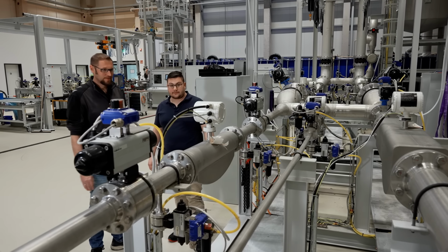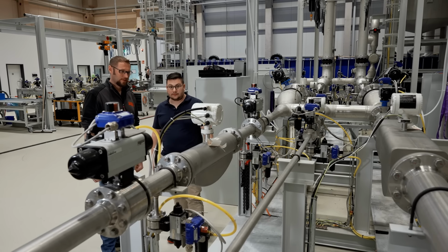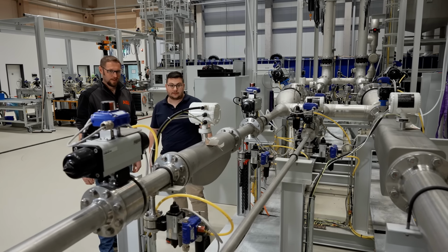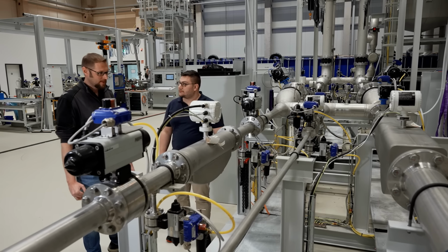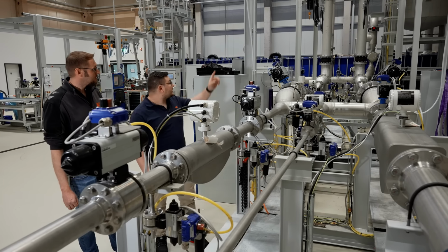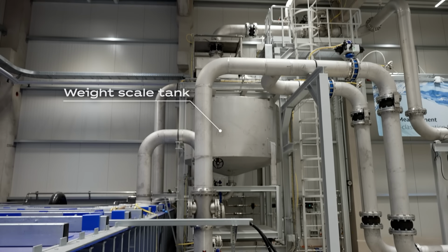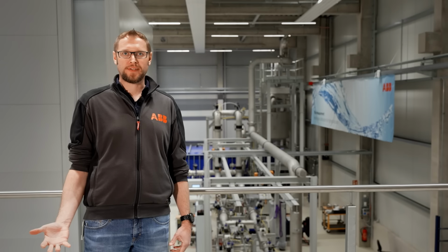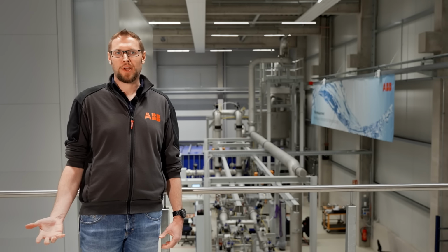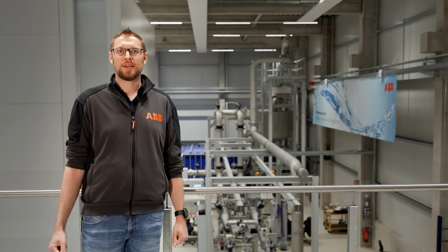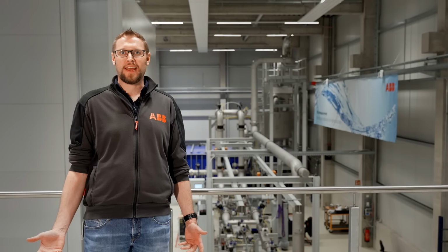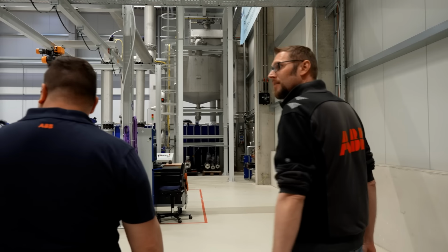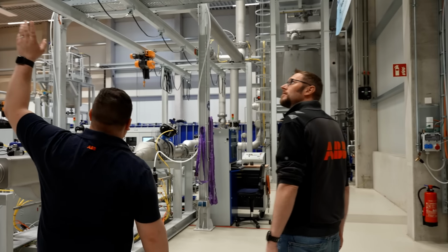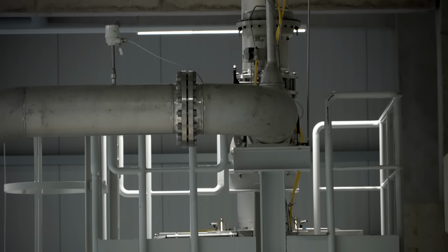Okay, so these master meters are only used for standard calibration, right? Exactly. And for the higher accuracy, we have the weigh scale tank. Yes, we have one. It's right in the back there. For accuracies up to 0.4%, we have a so-called master calibration, where we refer to a master meter with our meter under test. We have a calibration of our CoriolisMaster meter against a water weigh scale tank. Water comes out of the master meters, goes up this pipe, along the calibration rig, and all the way up to the top of the tower.